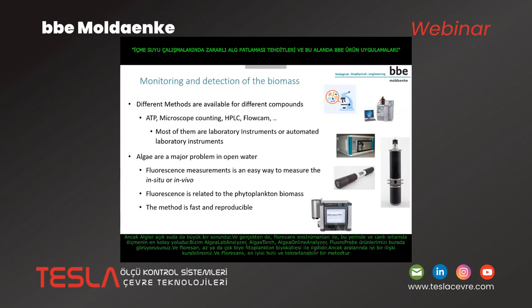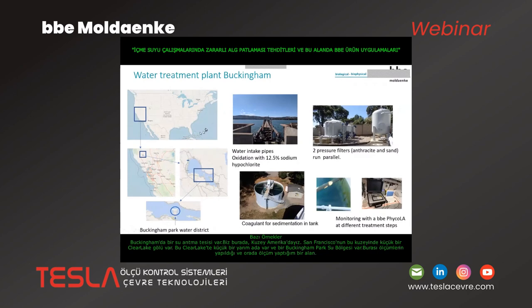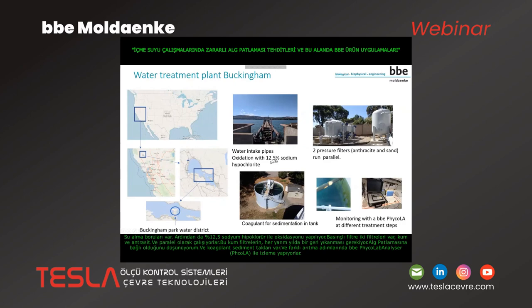Here we have a water treatment plant in Buckingham, North America — at Clear Lake north of San Francisco. At Buckingham Park Water District there are water intake pipes, after which they make an oxidation with 12.5% sodium hypochlorite. They have pressure filters — sand and anthracite running in parallel — and a coagulant sedimentation tank. They have monitoring with BBE FluoroProbe at different treatment steps, and we have worked with them together since 2019.